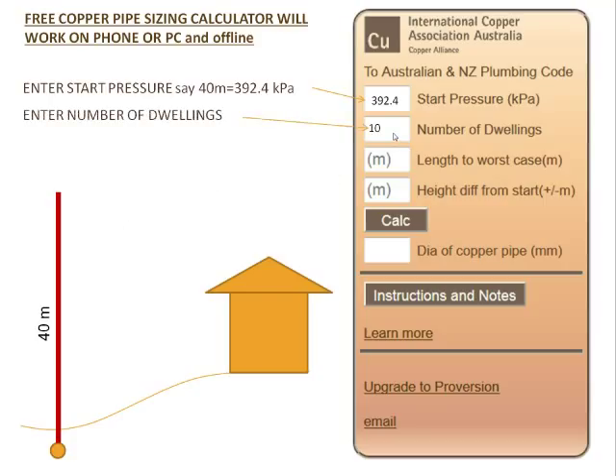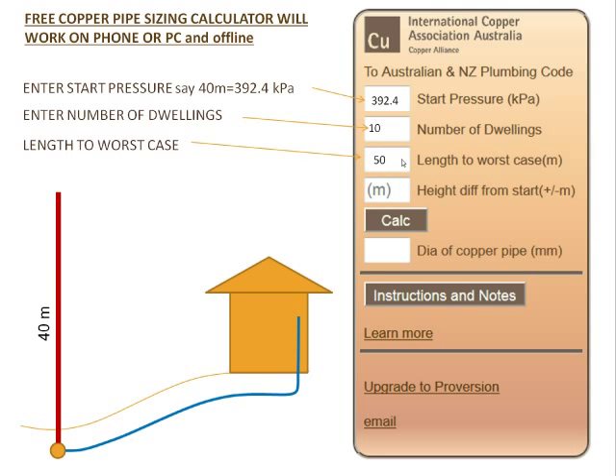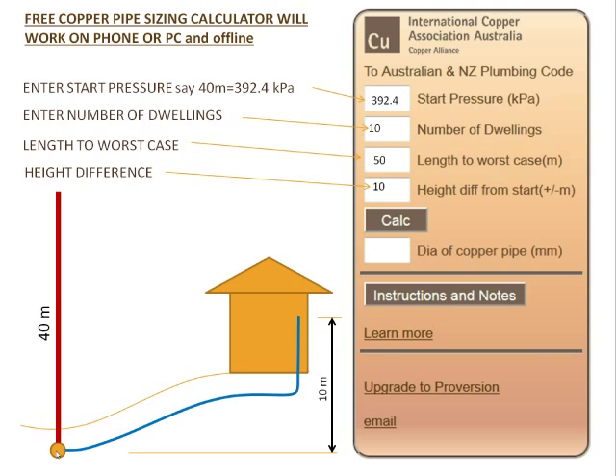We enter the number of dwellings — let's say 10 for argument's sake — the length of the worst case, say 50 meters, shown in the diagrammatic representation here. The height difference is 10 meters from the start, which is the water main, to the highest fixture. Press calculate, and up comes our answer of 32 millimeters diameter copper.